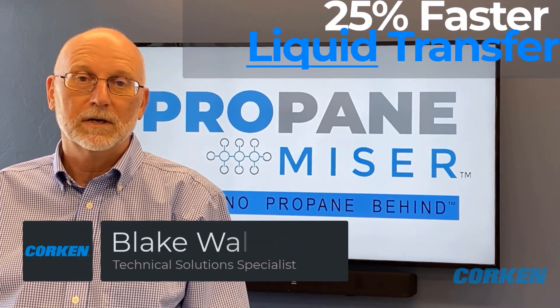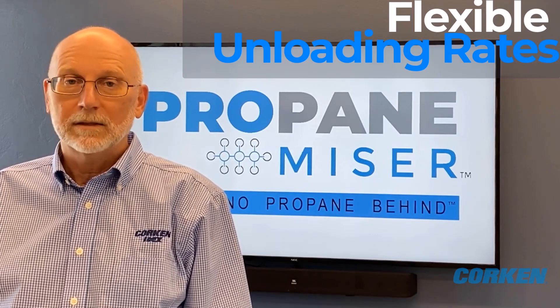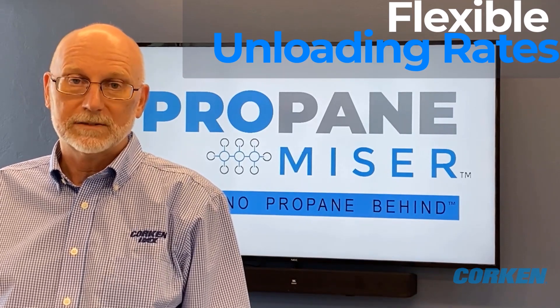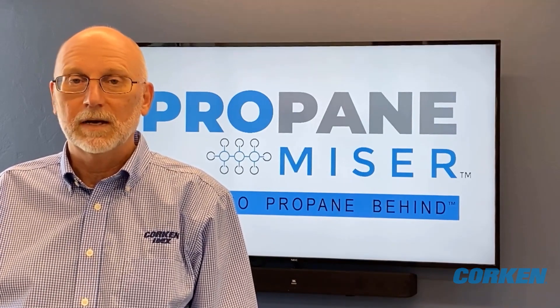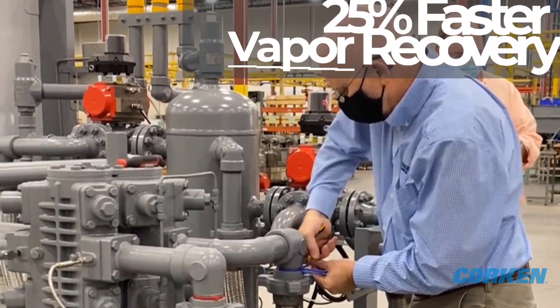The Propane Miser does four things well. Number one, it transfers liquid 25% faster than a current high capacity unloading compressor. Number two, it has a flexible unloading rate so you can transfer at that high capacity or at less than half of that capacity. So if you have a single rail car, a rail car with weak excess flow valves, or even a transport, you can unload that.